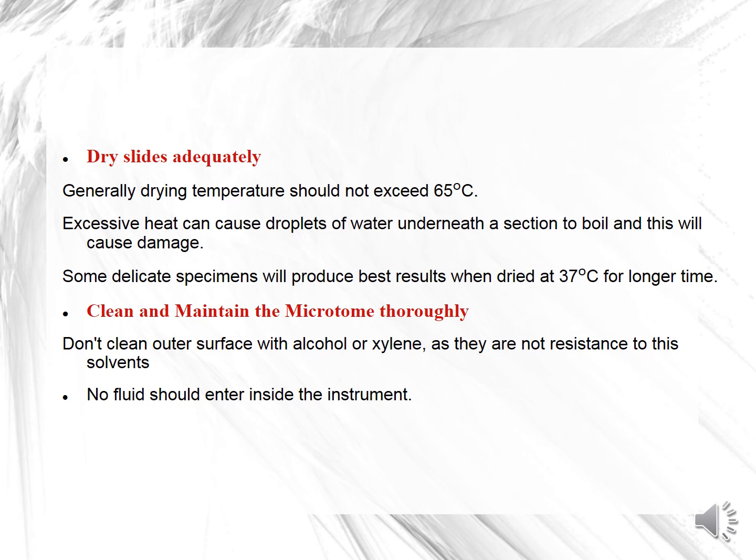Next, clean and maintain the microtome thoroughly. Do not clean the surface with alcohol or xylene, as it is not resistant to these solvents. No fluid should enter the instrument.